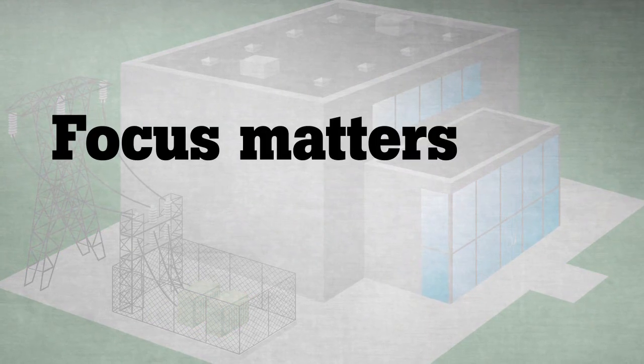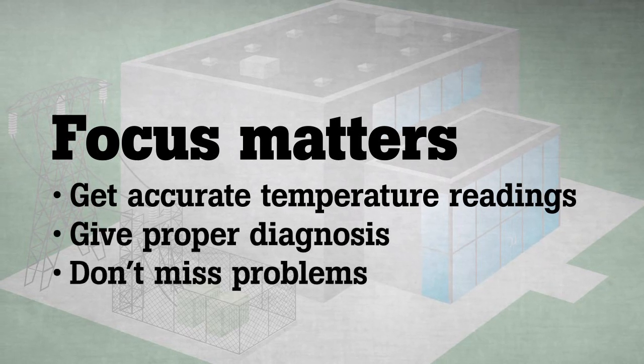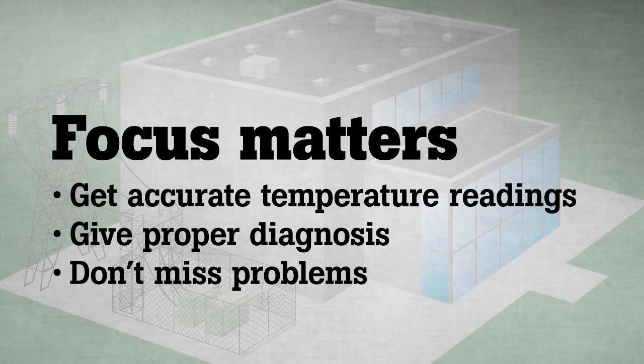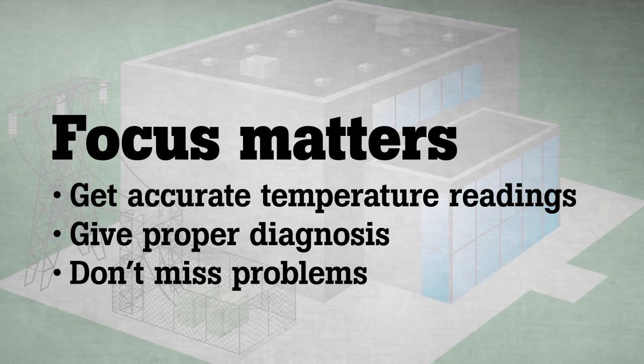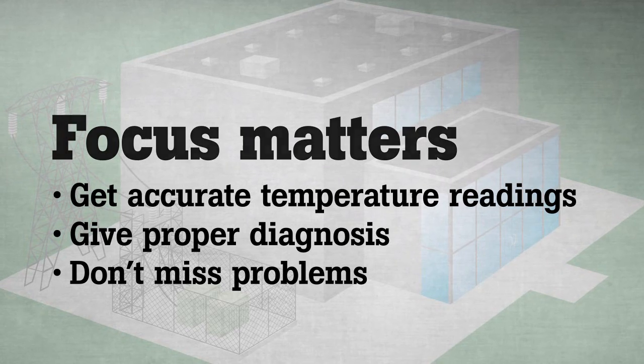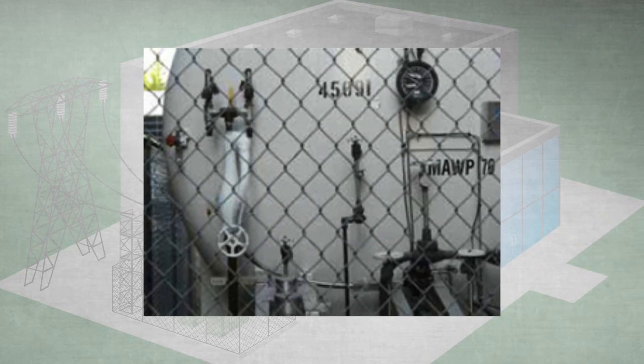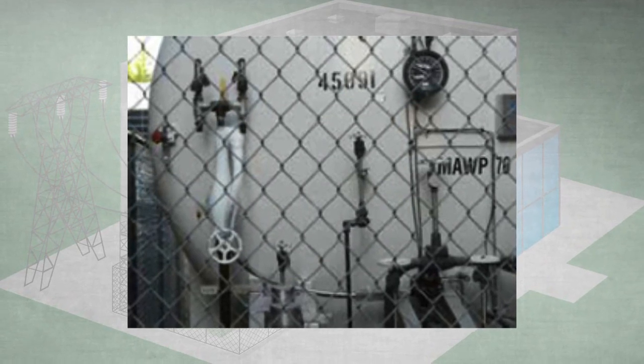Every infrared camera user knows that focus is the single most important thing to ensure when conducting an infrared inspection. Without an in-focus image, temperature measurements are often not as accurate, sometimes by as much as 20 degrees, and out-of-focus images makes it much easier to miss a problem.